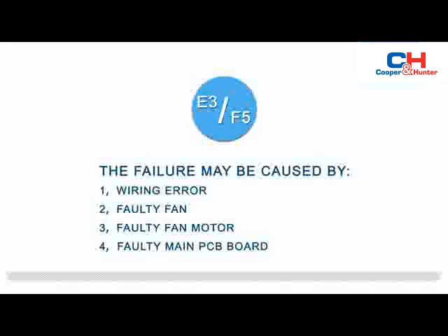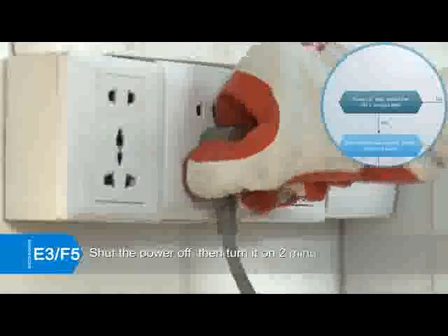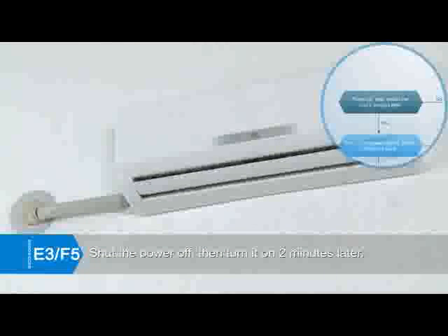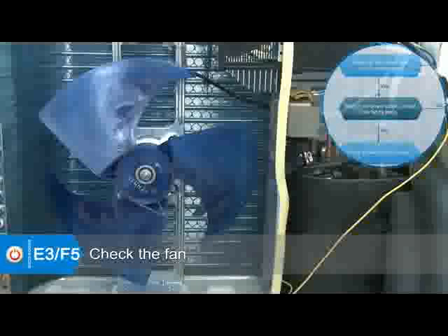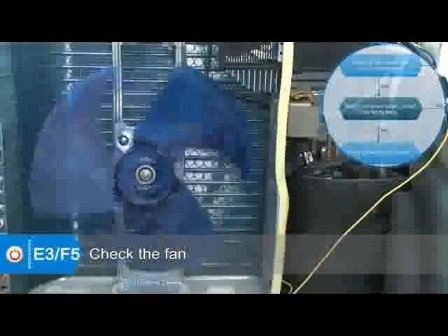The failure may be caused by: wiring error, faulty fan, faulty fan motor, or faulty main PCB board. First, shut the power off then turn it on two minutes later. If the error still exists, shut the power off, then check the fan — rotate it by hand to check whether it is blocked or rotating normally.